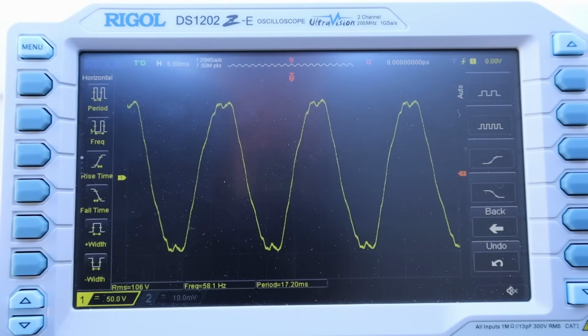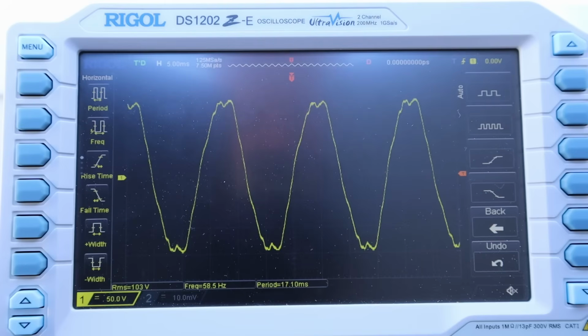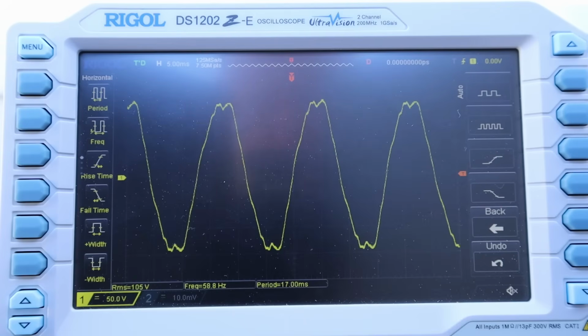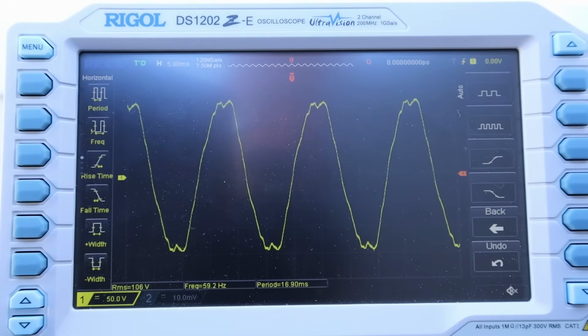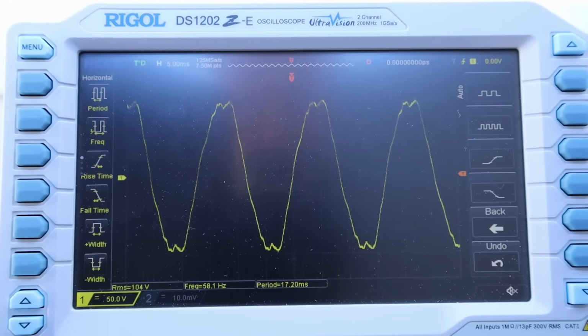With the generator running that 3,000 watt load, I've connected the oscilloscope again, and the sine wave is quite changed from before. The voltage is showing right around 104 volts, and the frequency is about 57 to 58, maybe up to 59 hertz. That sine wave output is just not acceptable for any sensitive equipment you'd ever want to connect to this thing.